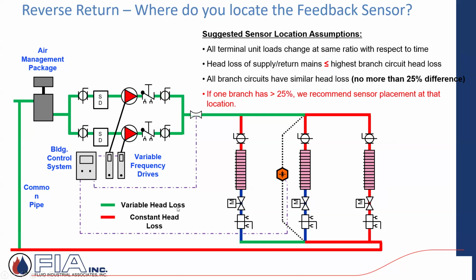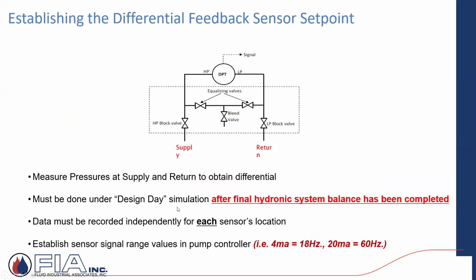Suggested sensor locations, where do you locate it? Some assumptions: all terminal unit loads change, same ratio. Might be true, might not be. Head loss of the supply and return mains, the distribution mains, are less than the highest branch circuit head loss. All branch circuits have similar loss, no more than 25% difference between them, meaning all the different fan coils that we're using with the control valves. So there are some little rules of thumb you want to acknowledge relative to sensor location. And this is just getting very specific with your DP, differential pressure readouts, if you will, where your sensors are. What type of measurement? What does it mean? You might be telling the VFD drive what 4 mA milliamp represents for hertz, etc. That's up to the individual drives.